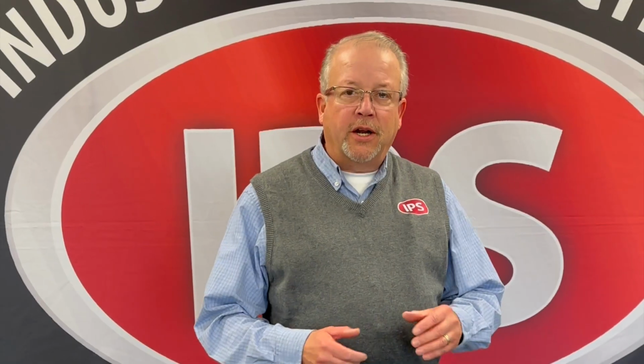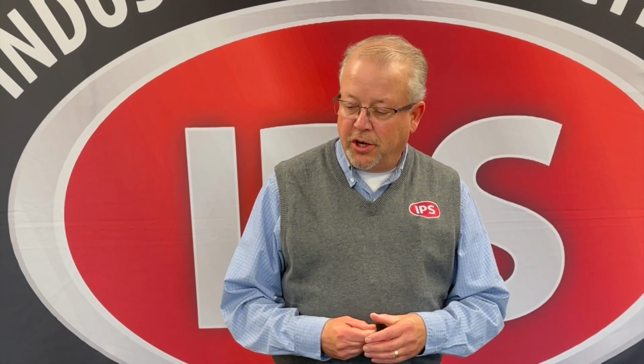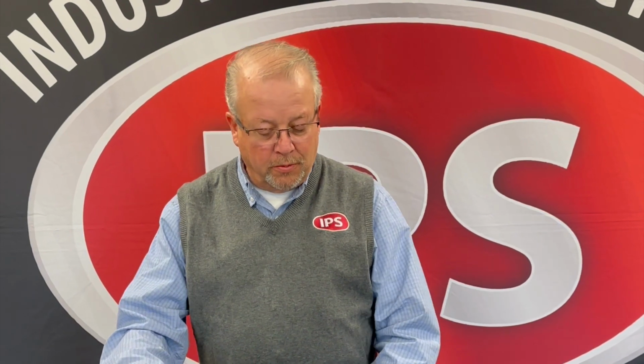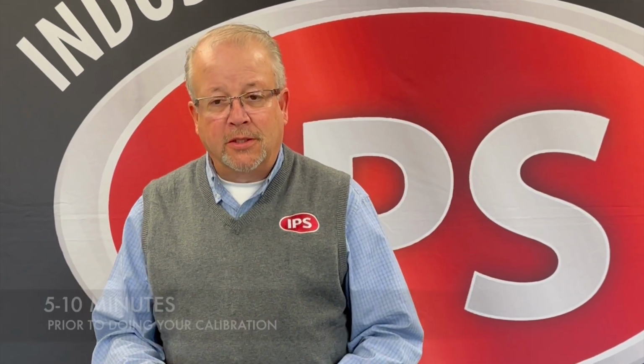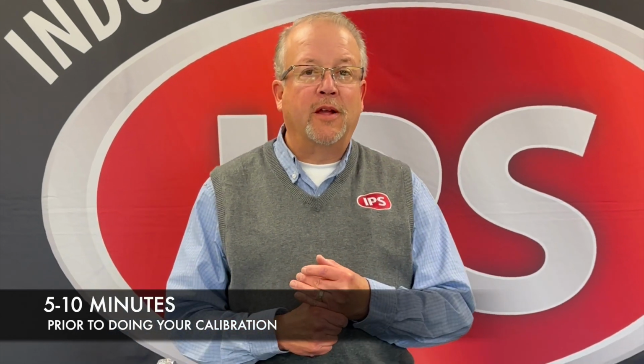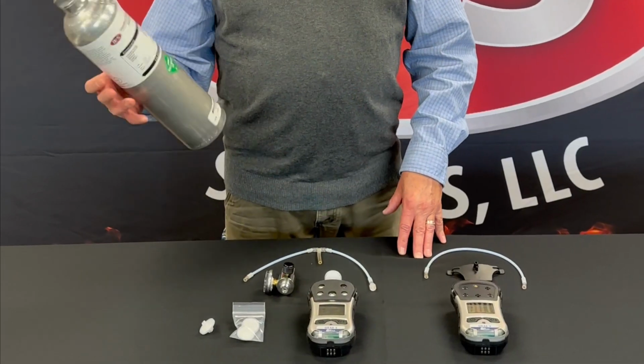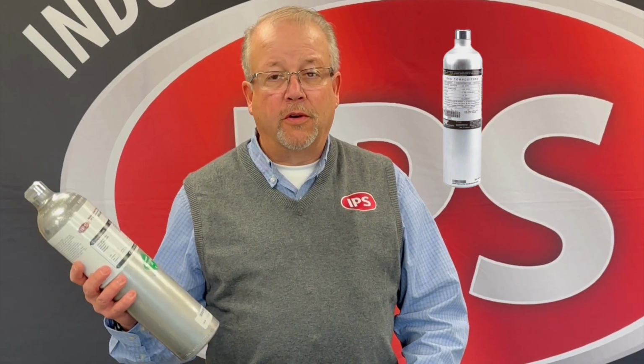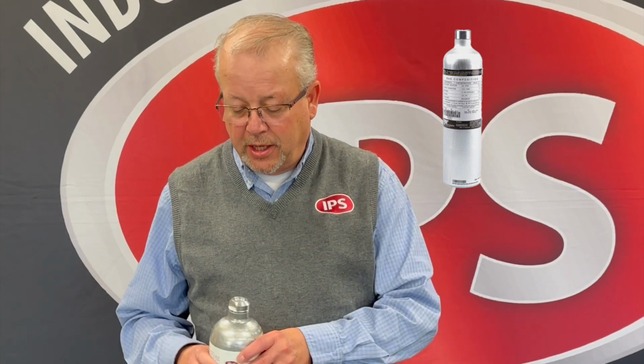Before you start doing your calibration, you want to make sure you have all the right components and that your monitor is up and running. Best practice is to let it run for approximately 5 or 10 minutes prior to doing your calibration. During that time, you can get your supplies ready. I've got a 4-in-1 mix, or what we refer to as the 4-in-1 mix calibration gas.